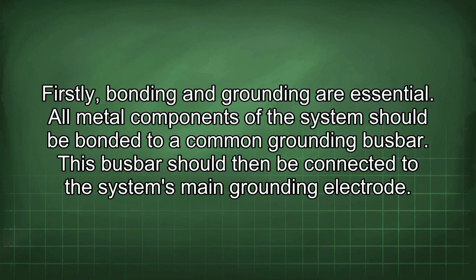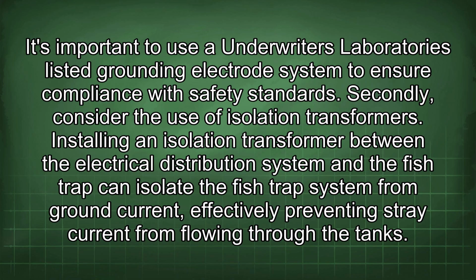Firstly, bonding and grounding are essential. All metal components of the system should be bonded to a common grounding busbar. This busbar should then be connected to the system's main grounding electrode. It's important to use Underwriters Laboratories listed grounding electrode system to ensure compliance with safety standards.